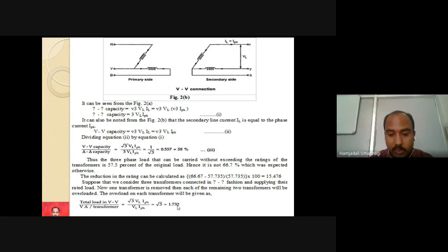This is the work which it has to take care of, and this work is taken from the out of service transformer. Once the connection becomes open delta, then each of these 2 transformers has to carry 1.732. It means that apart from its own loading condition, that is 1, that is 100%, it has to carry an extra load of 0.732. That is the meaning. It is similar to when 3 friends are given some work for some task. If one of the friends, due to some reason, is absent, then the work that the third friend had to do will now be done by the other 2 friends.